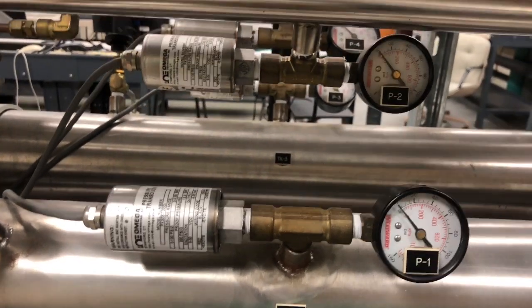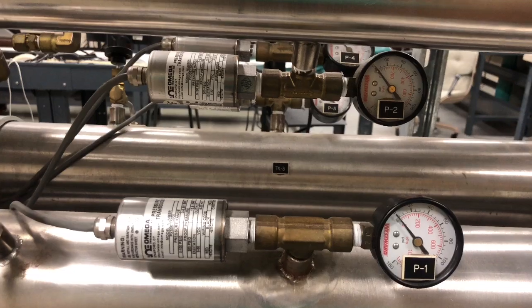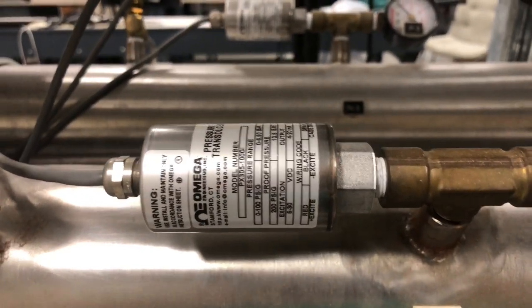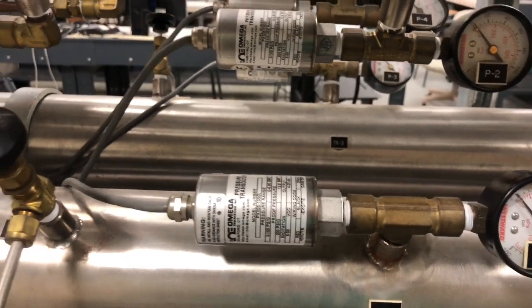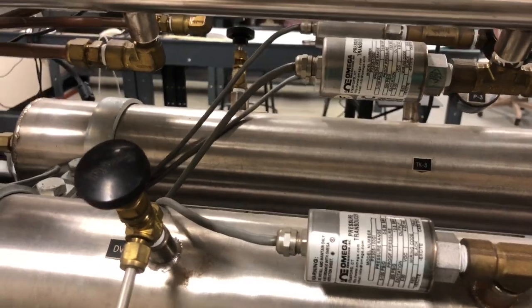And you can see it looks like a lollipop. It sticks off the side, and as you change the pressure, the needle will go around that dial. At the same time, there's a piece of electronics there that is exposed to the tank. It converts the pressure value to an actual measurement to go back into the data acquisition system.